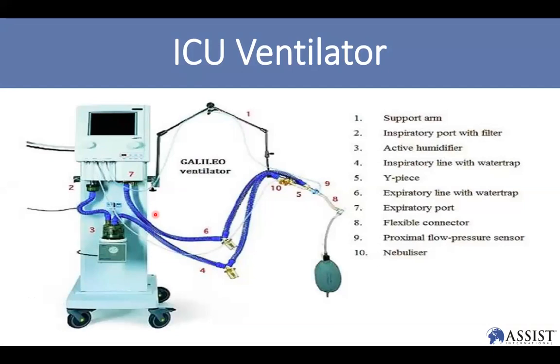You've all seen a ventilator perhaps at your facility that looks something like this. Some key components involve a support arm that helps keep the patient circuit stabilized. We've got an inspiratory port right about there with the filter attached to it. We've got active humidifier. We've got an inspiratory line with a water trap. And then we also have a Y piece. This is a critical component. We will reference this later on. We've got an expiratory line also in some cases with a water trap.